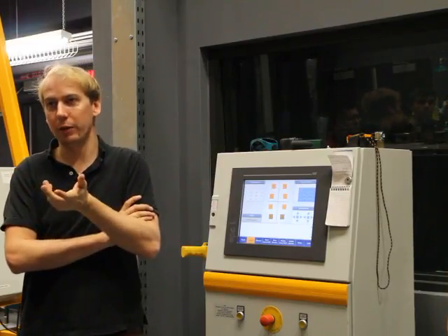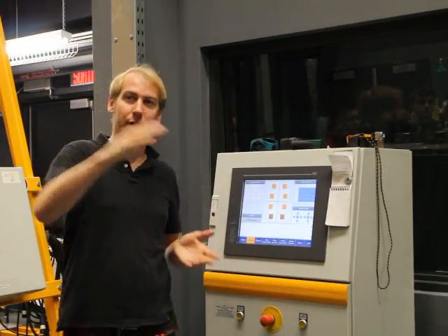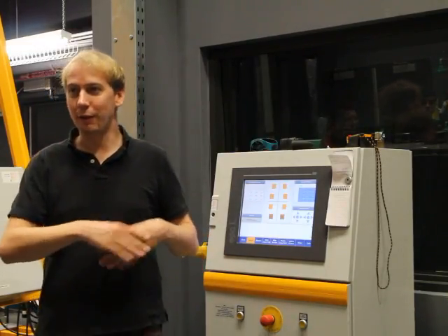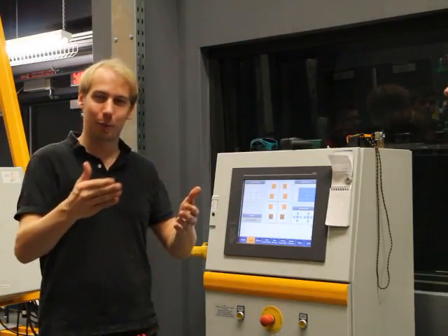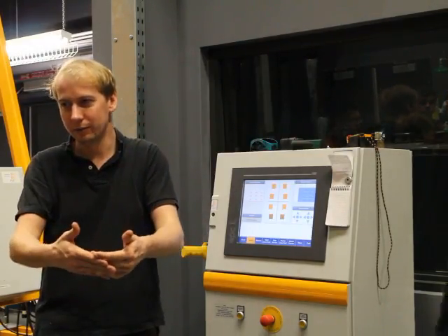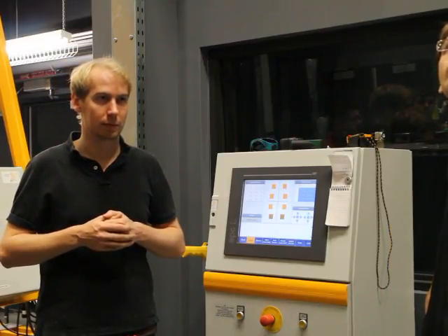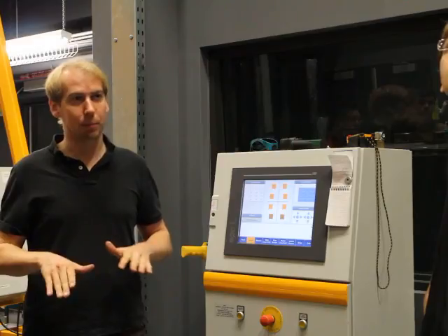The problem will also be, if you go way below 1.50 meters, the intensity on the test platform will be very high, so you have to dim the lights a lot. What is also my suggestion: never start at 100%. Go to 90, so you can go a bit lower and a bit higher. What's driving everything is homogeneity. That's your target, and that's what's driving placement of the lamps and distance. Yes, pretty much, for flat plate things, I would say yes.